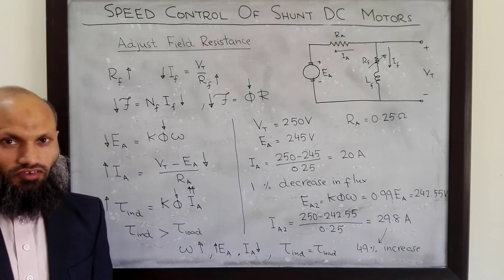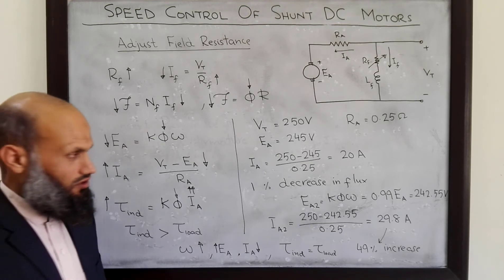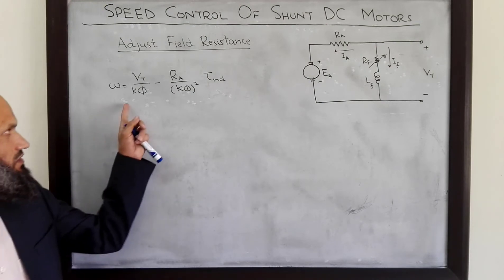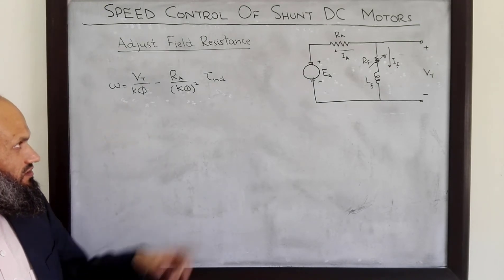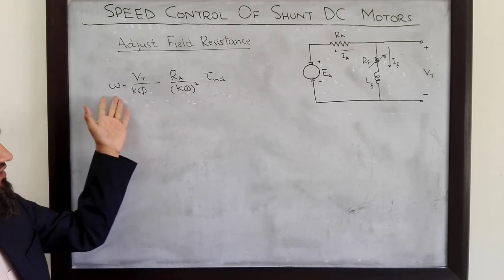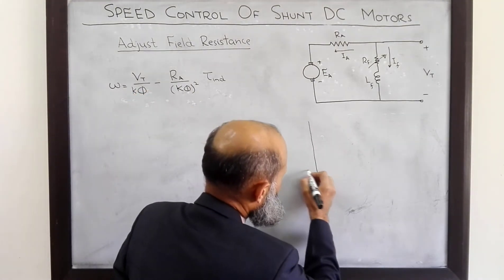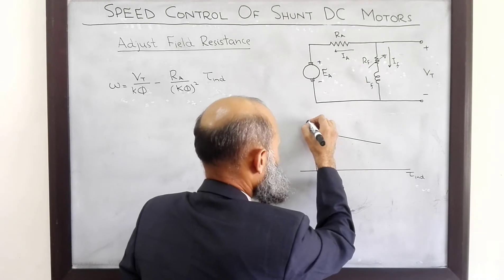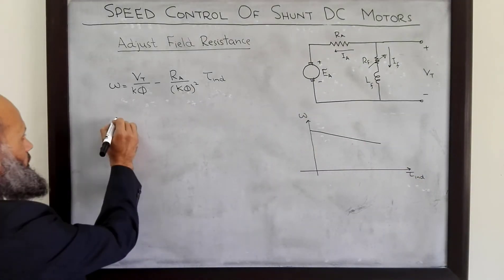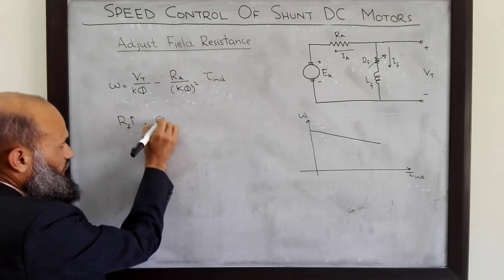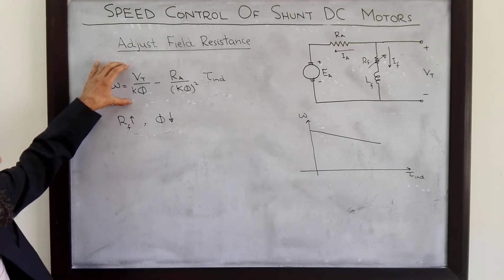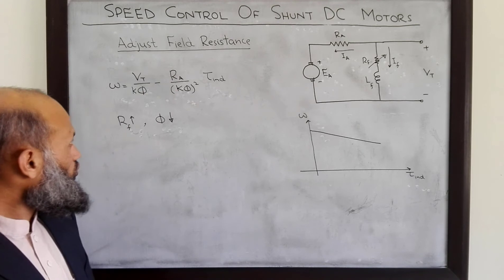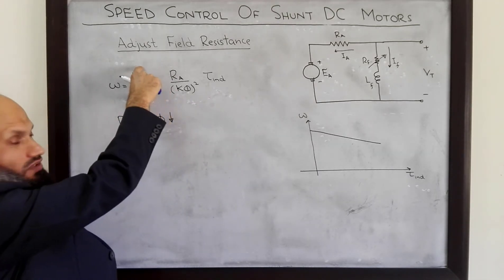This effect is also apparent from the torque-speed characteristics derived in the previous lecture. The expression relates induced torque with the speed of the motor — it is an equation of a straight line with a negative slope. If RF is increased, flux decreases, and this quantity in the denominator increases, so the slope becomes more negative and the intercept on the vertical axis also increases.